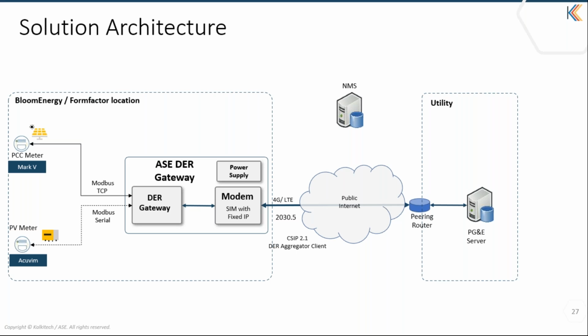So the requirement was to connect 2 meters, one PCC meter, which was Mark 5 meter, and another PV meter, which was the manufacturer Acuvim. So from these meters, the data had to be collected into the DER gateway. With the Mark 5 meter, we collected data through Modbus TCP. So the gateway has a LAN port, and using that port, we could connect to any TCP device like DNP3 or Modbus or any other standard protocol. We could get the data into the gateway. So we utilized that functionality to configure the gateway to match the network addressing of the site, and collected the data from the Modbus device.